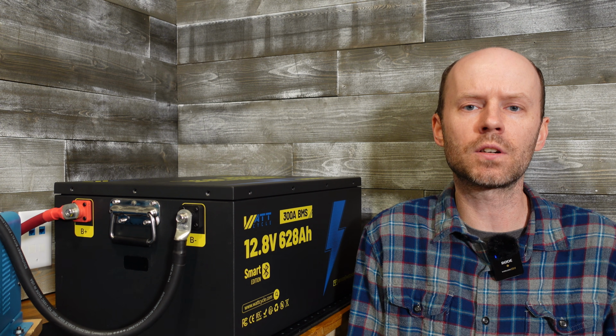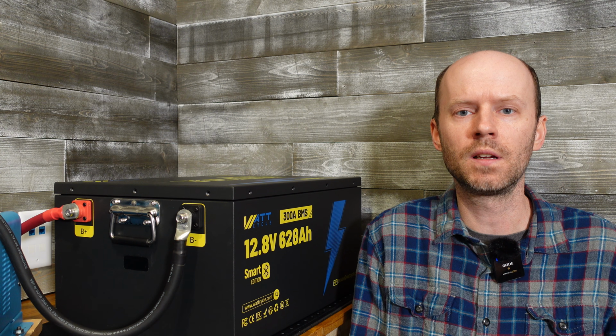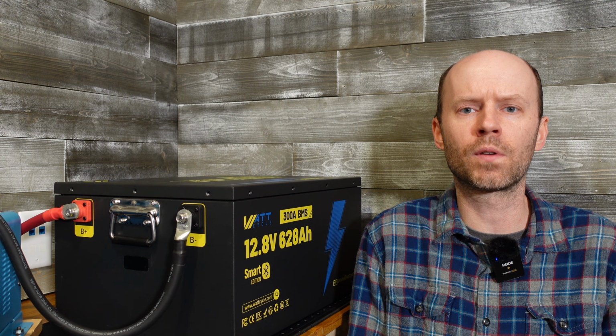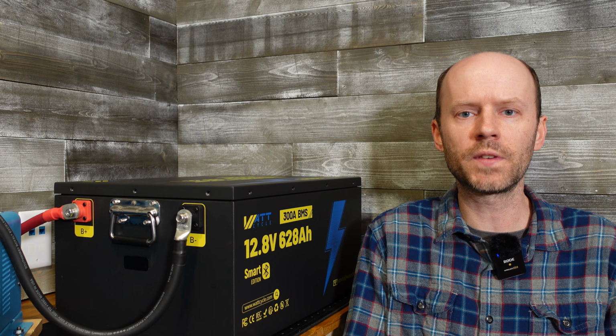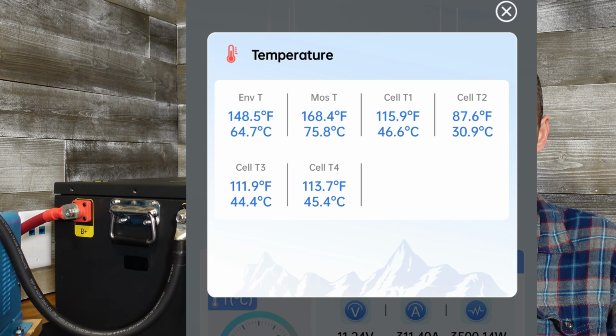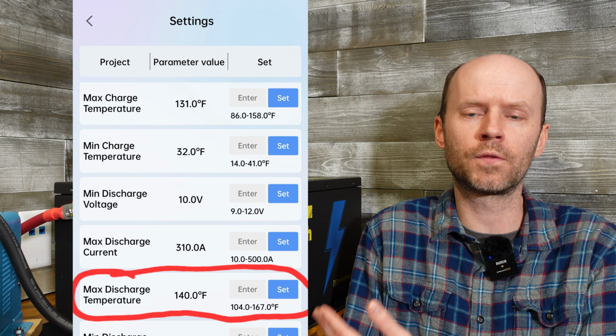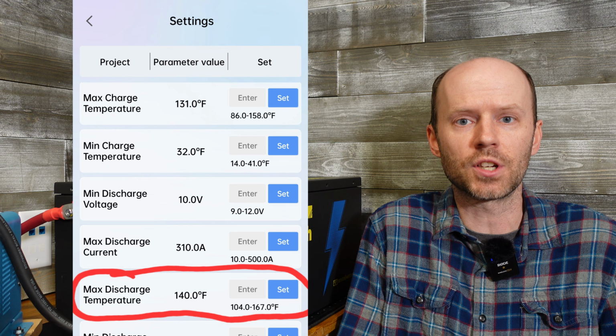As the voltage began to drop near the end of the test, the current started to increase as we expected, and we actually ended up tripping the overcurrent protection of the BMS at 310 amps. The MOSFET sensor was reading 168 degrees Fahrenheit, and the ENV sensor was reading 148 degrees Fahrenheit. So the next question then is, if this is programmed for 140 degrees Fahrenheit, why did it not shut down?